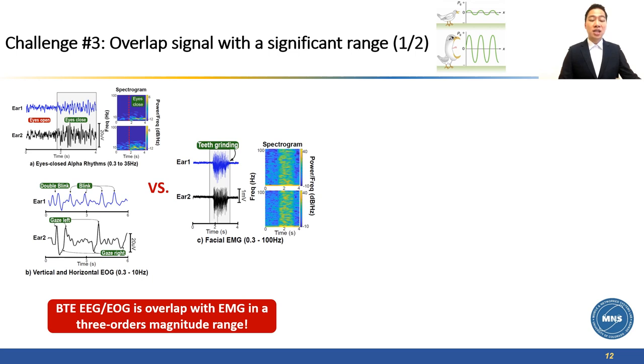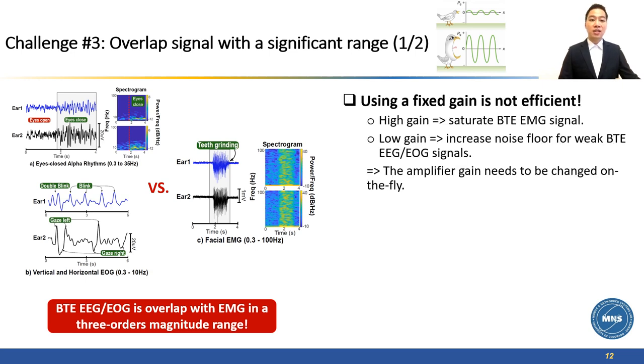One of the challenges that we notice with our behind-the-ear signal is the overlap between EEG, EOG, and EMG signals in three orders of magnitude ranges. As a result, using a fixed gain is not efficient. Using a high gain to have a better resolution for EEG and EOG can saturate EMG signal. On the other hand, using a low gain to avoid saturation will increase the noise floor. To handle this issue efficiently, the gain of our amplifier needs to be changed on the fly.